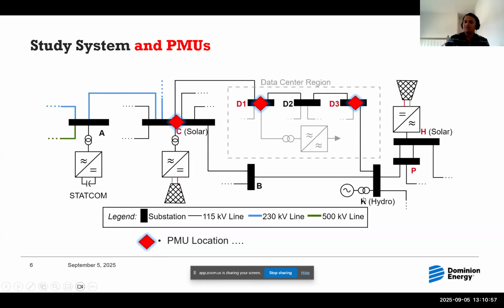The hydro units we took out, which triggered the oscillations, were at substation K. We took them offline and the oscillations started. We have pretty decent coverage in this part of the system — PMU data at the substations where the data center is connected, at neighboring solar, and even at the STATCOM and hydro units.